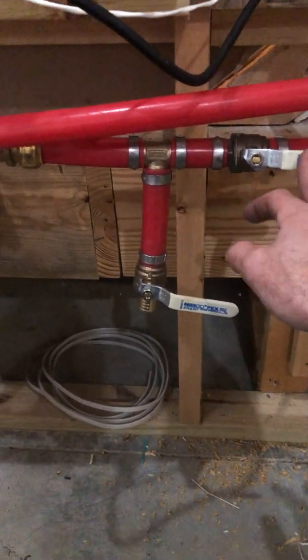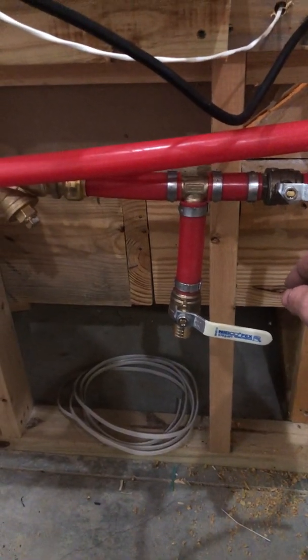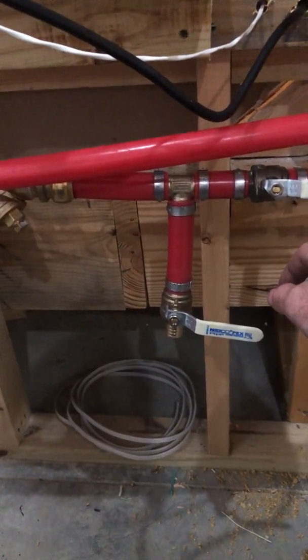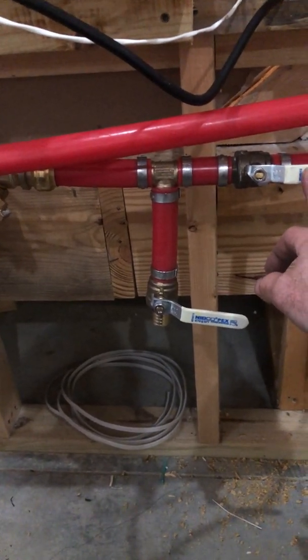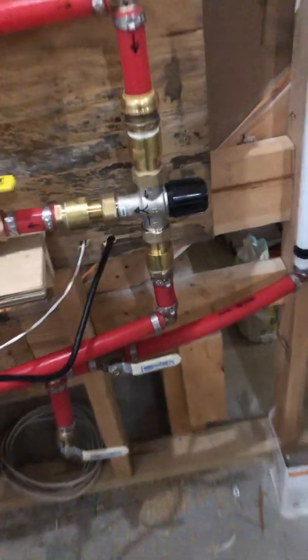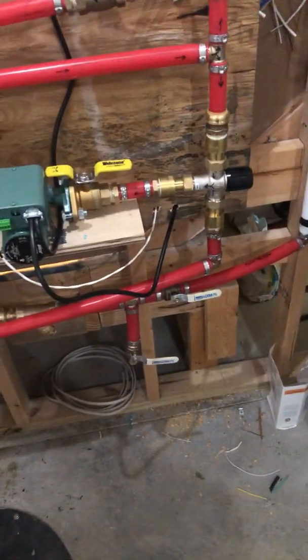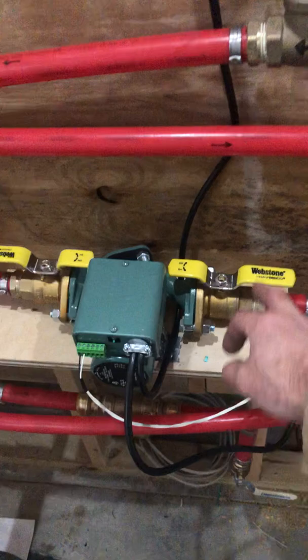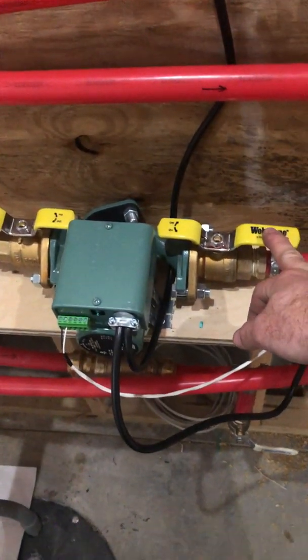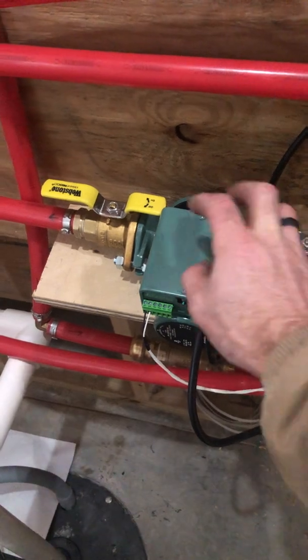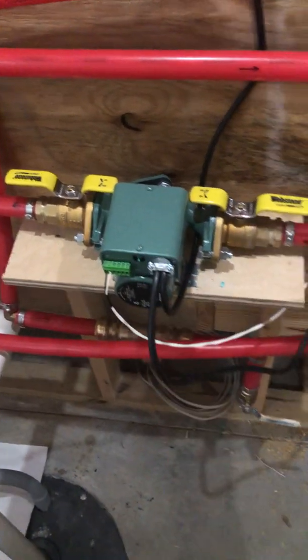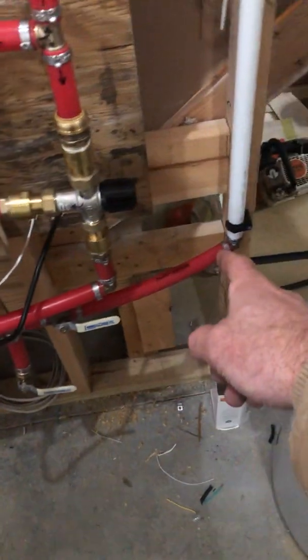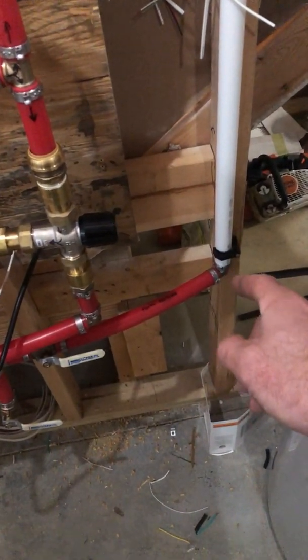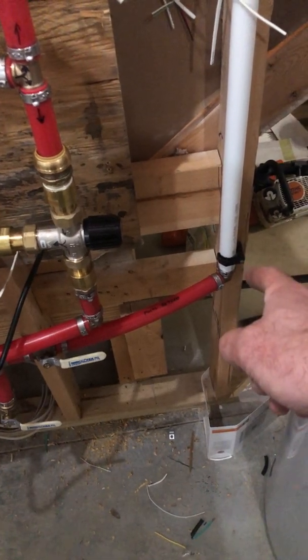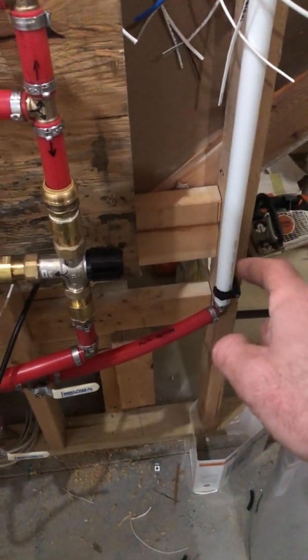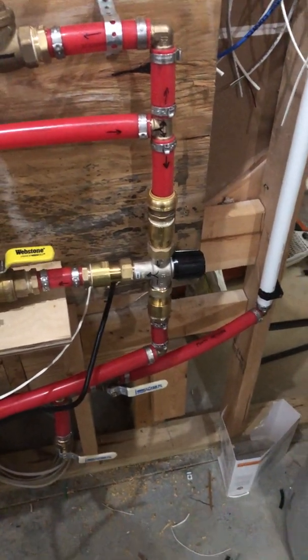That is one thing I will say, when you go to set these systems up, you're going to need more ball valves and more fittings than you anticipate, but that's cool. It's fine to set it up to where you can bypass, because if you do have a problem, it'll be a pain in the ass not to. I put these flanges everywhere I could, so that way I can turn this off and service the pump if need be. And then I bought two 100-foot rolls of red 1-inch, and I only needed like 20 feet, so I did some white, which I didn't like doing, but it is what it is.